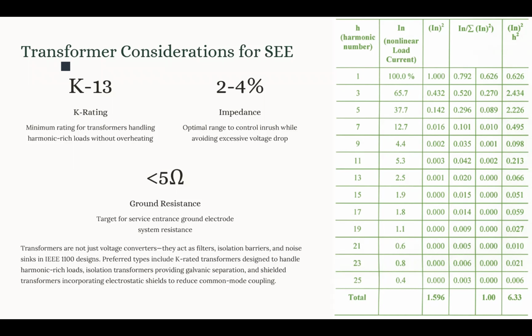Another criterion for choosing the transformers in our power system is the impedance rating. The recommendation from IEEE 1100 is an impedance range of 2 to 4% in standard power frequency impedance. What is the rationale? Low impedance, less than 2%, allows high inrush currents, which causes breaker tripping or voltage dips for other loads. If we have higher impedance, more than 4%, it means excessive voltage drop under dynamic load changes. So this standard requires an impedance between 2 and 4%.